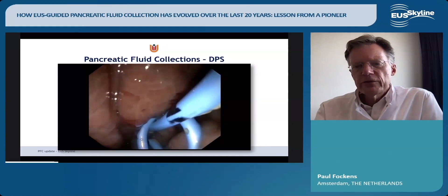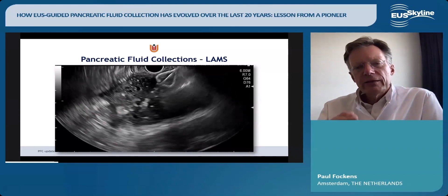As you can see, we check for vessels. And then with the first step of the Axios, that's number 1, you go in deep. The second step then will be to develop the inside flange, as you'll see in a moment. That's step number 2. And then step number 3, you always need a little bit of time for that to change. You can remove the connection, the cautery, etc. And then you have to pull that stent close to the wall because you don't want to lose the stent inside. And when you really pull it quite snug and you see this tip of the stent hitting the introduction system, then usually you know for sure. You open it inside the endoscope and then slowly push it out. And that's the way to do it. I think Michel Kahaleh probably has made a point that you can then continue immediately with a direct necrosectomy.